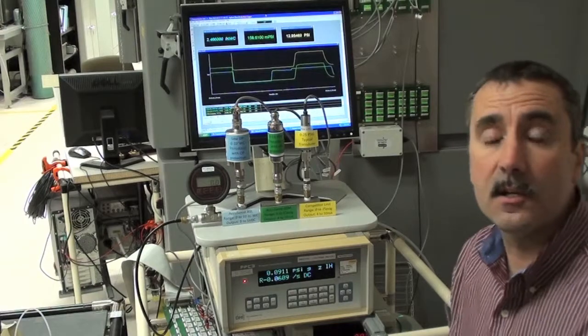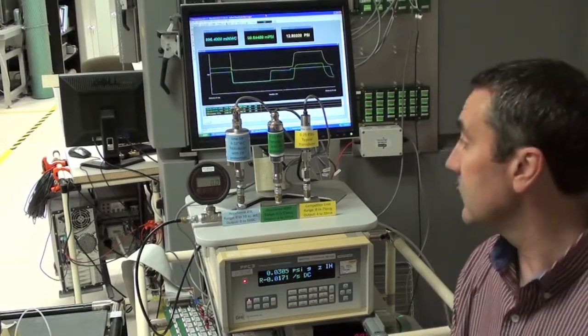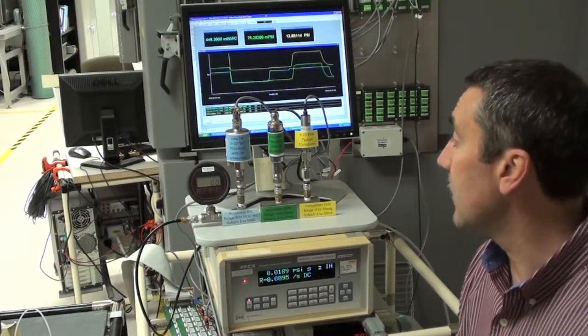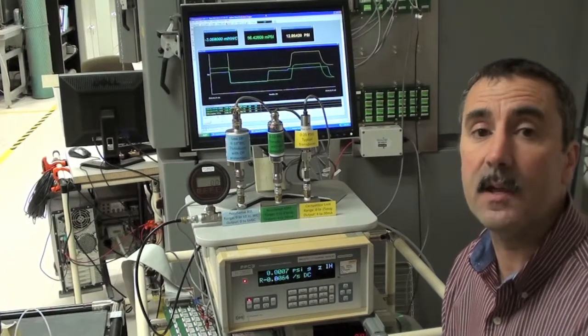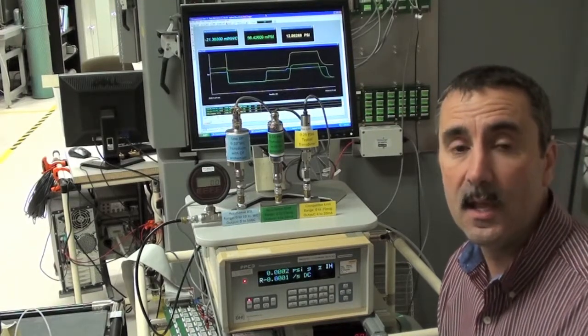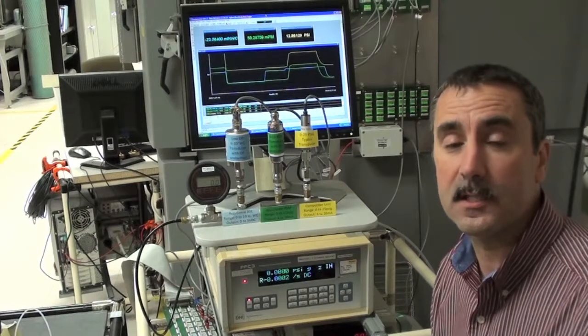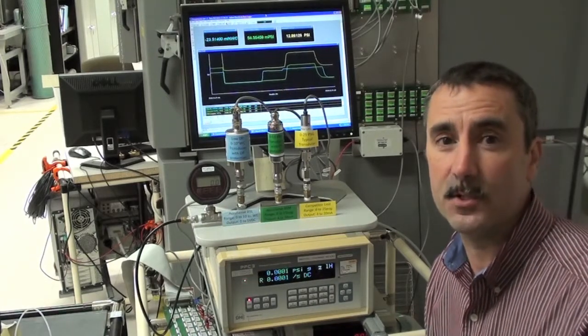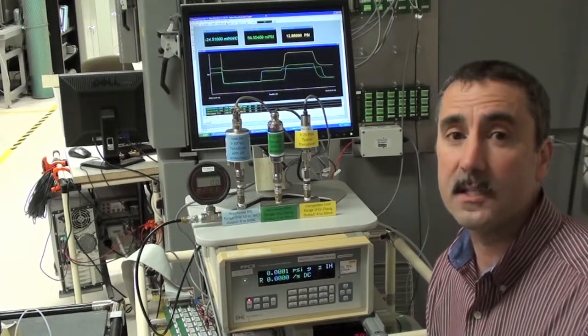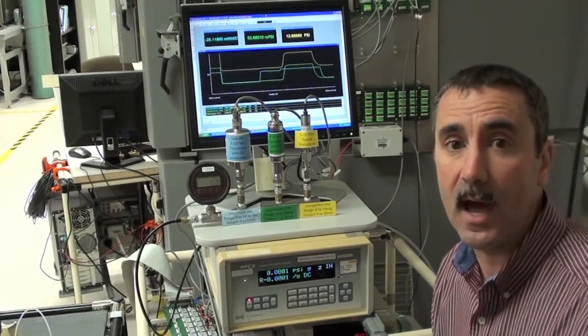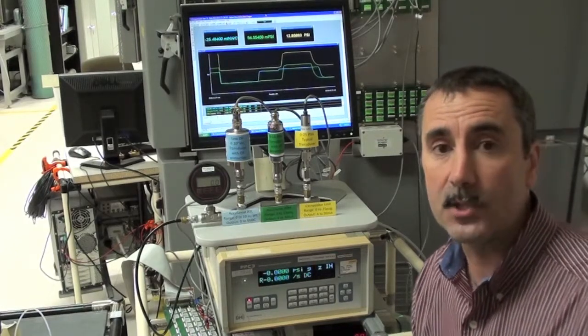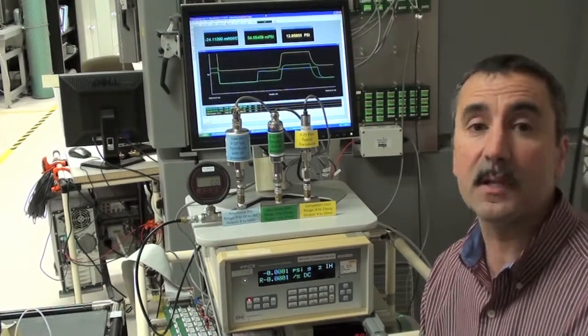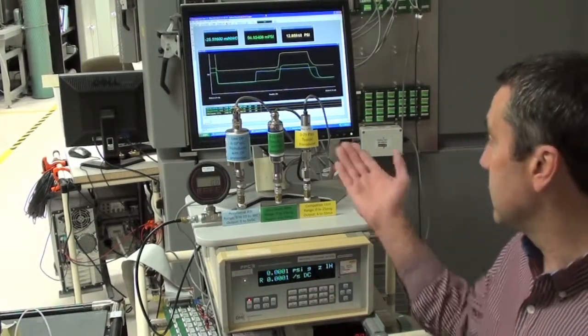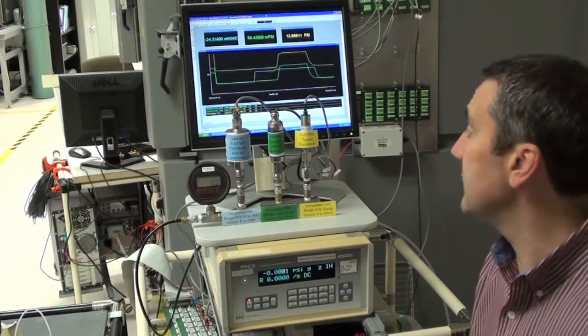So there it is. This concludes our experiment, and showing that there are products, transducers on the market that have very high overpressure protection, and that's a very important specification, especially for applications where unintended overpressure can occur, or a system can apply periodic overpressure events which would typically damage a typical pressure transducer if it did not have high overpressure protection.